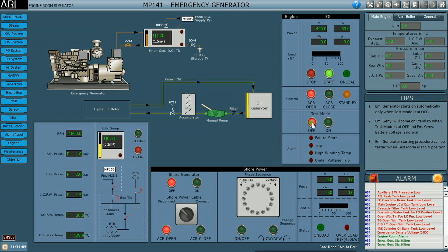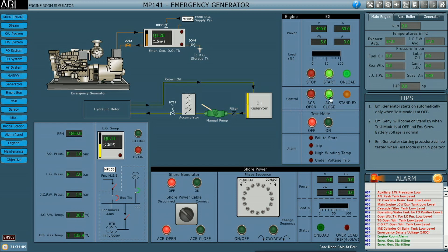When I switch off the test mode, the ACB will close automatically and the generator will come on load. These are the two methods by which we can start the emergency generator. If your emergency generator is on standby, it is going to come on load within 45 seconds of a blackout condition.